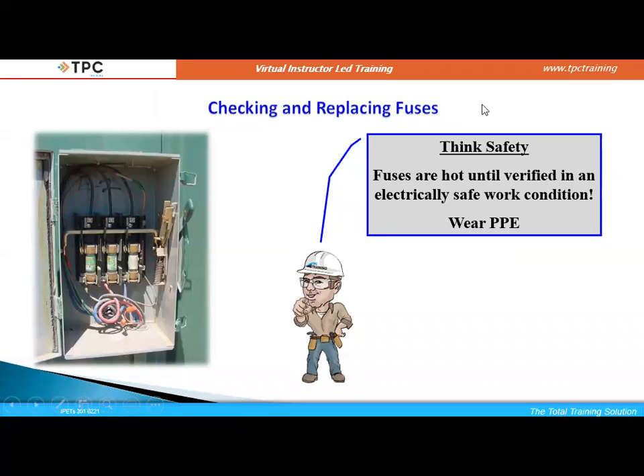And so I already said this, that if we are going to check and replace a fuse, the safest way is this. We want to de-energize this whole disconnect. And so I am going to go to the upstream overcurrent device, wherever that is. I am going to perform the steps needed to establish an electrically safe work condition. So I'm going to find the source for this. I am going to make sure that I have shut off the equipment. These fused disconnects are not load break devices. So first I'm going to hit a stop button or whatever it takes to have no current flowing through this. And then I am going to shut off the upstream overcurrent device and perform live-dead-live here. I will have already locked and tagged out that upstream overcurrent device.